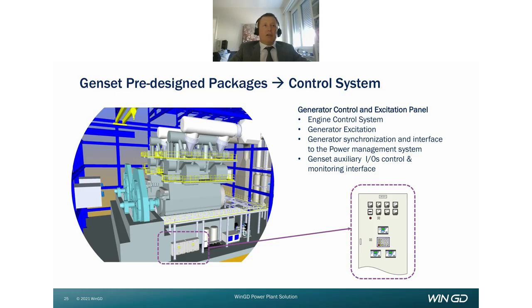The genset and the associated auxiliaries are monitored and controlled by the Generator Control Panel, hereafter called GCP. The GCP is the brain of the genset and represents the single point interface between the genset and the plant automation. During the normal plant operation, the GCP is set in remote mode and it manages the genset start, stop, and synchronization to the medium voltage bus upon receiving a command from the Power Management System, or PMS. In this mode, the GCP acts as a slave and the PMS is the master control.